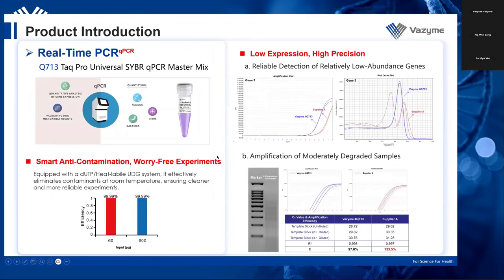Next is the real-time PCR itself. This is where the quantification step starts. For this, we have Q713. One of the things that we want to highlight is the anti-contamination system, which is the dUTP heat-labile UDG system. What this does is make sure that your qPCR reaction will not be contaminated by the qPCR reaction of the previous step.